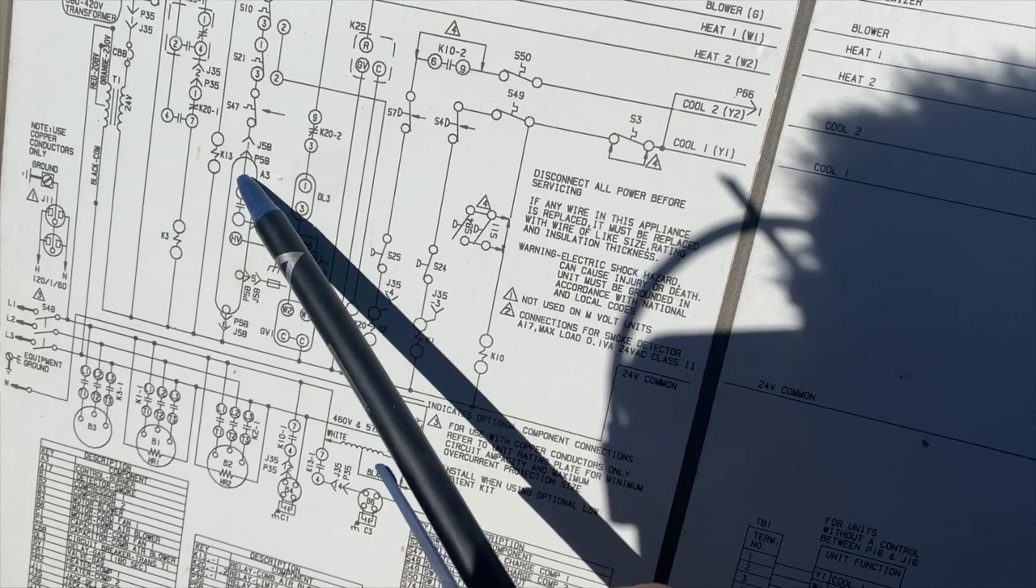When the inducer is powered up or cycled on, this guy's going to close which is going to power up our ignition module. There's actually 24 volts always going into it, so it's going to go ahead and call for the ignition when that switch closes. I'm starting to think that we may have an issue with this, however I want to make sure I'm getting that power to the module. If this is not closing I should have no power here. If it is closing I should have power here. If I have power here then that means that my module is no good. If I have power here it's the module, if I don't have power then maybe the switch isn't closing.